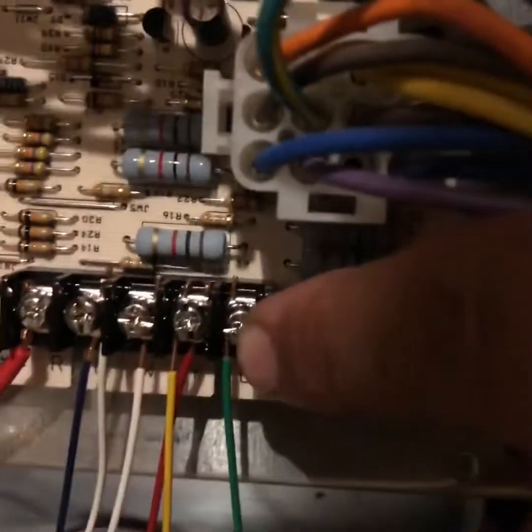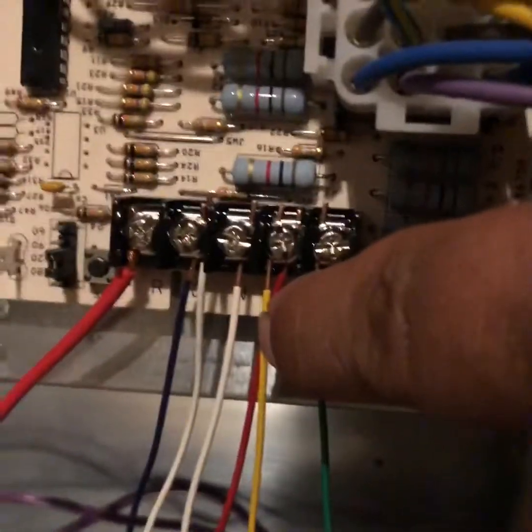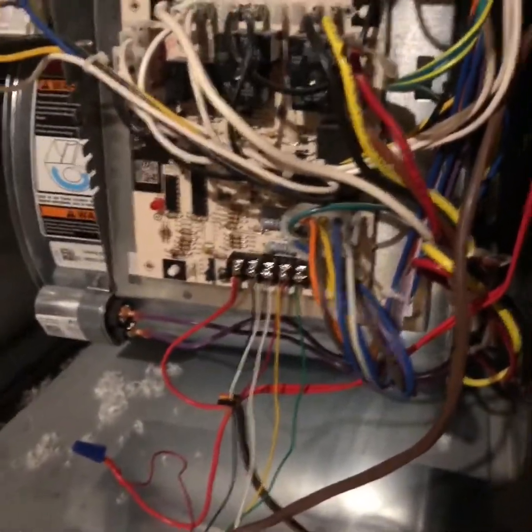Here it is once it's done. G terminal is for your fan, Y is where your two-wire from your outdoor unit and the yellow wire from the equipment tie in, W is your heat wire, C is your common, and R is one side of your safety switch — the other side is broken by your actual power wire. So if anything ever happens, the float switch pulls up, cuts the power to the board. Equipment is now wired up.